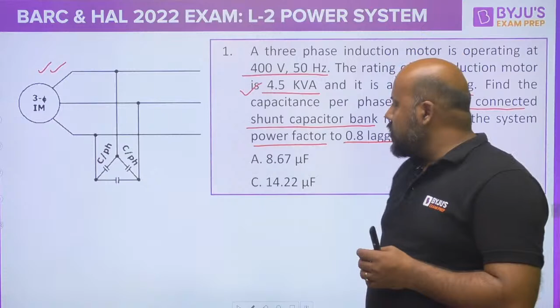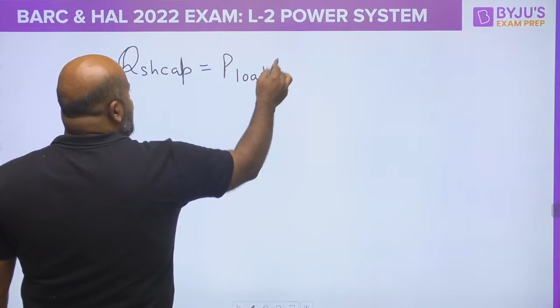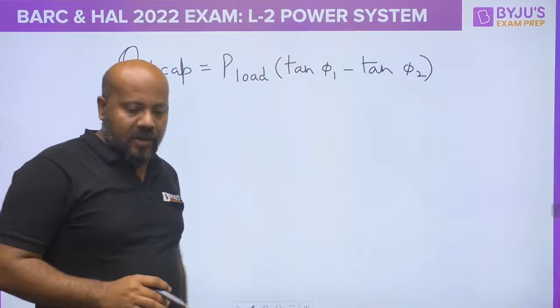The first thing you should understand is you can use the direct formula. The reactive power supplied by the shunt capacitor bank, directly you can write, and that is the formula: tan phi 1 minus tan phi 2. If you are not comfortable with this formula, just tell me in the comment section, and I will explain a little bit how this formula is coming, then you will be able to understand what I am doing here.